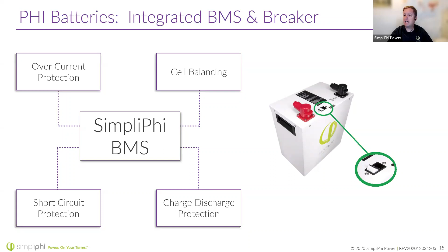One thing to keep in mind about our batteries is that we have a C/2 rating. A C rate is the rate at which a battery can be charged or discharged relative to its maximum capacity. So with the SimpliPhi Power 3.8 battery at 48 volts, it's a 75 amp hour battery. That means you can charge or discharge that battery at 37.5 amps continuously at a 48 volt rate.